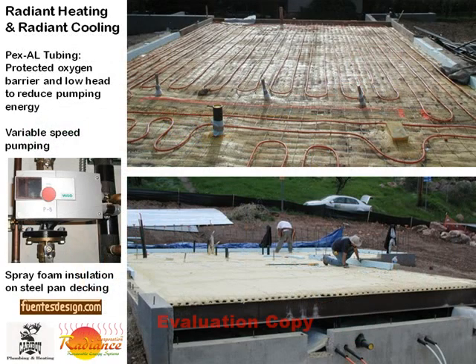Fuentes' design favors the utilization of steel pan decking in its floor construction to reduce framing resources. Radiance and Fuentes agreed to install spray foam insulation on the pan decking to bolster the radiant heating and cooling performance. The tubing used in the radiant floor is a special type called PEX-AL, which uses a protected aluminum foil oxygen barrier. PEX-AL also reduces head pressure of the system by about 15% compared to other radiant tubing, reducing pumping energy requirements. Heating or cooling water is circulated using variable speed pumps, further reducing pumping energy requirements.